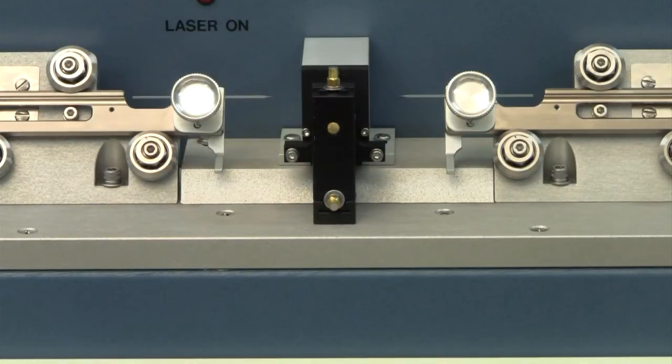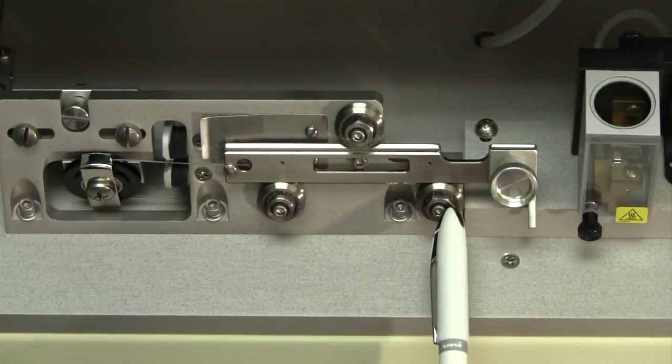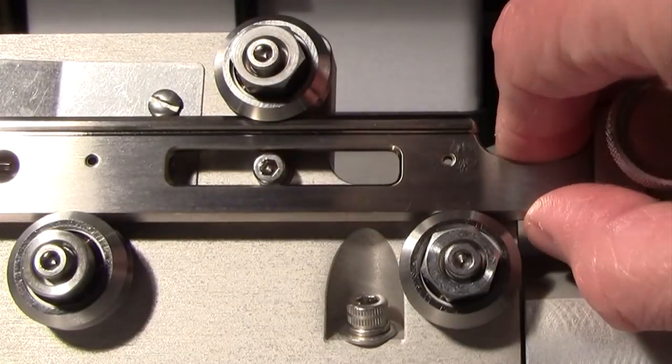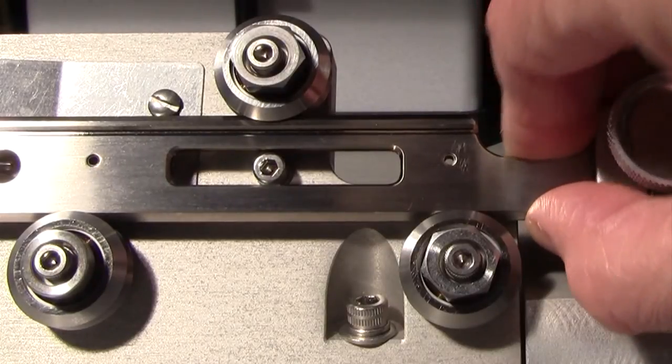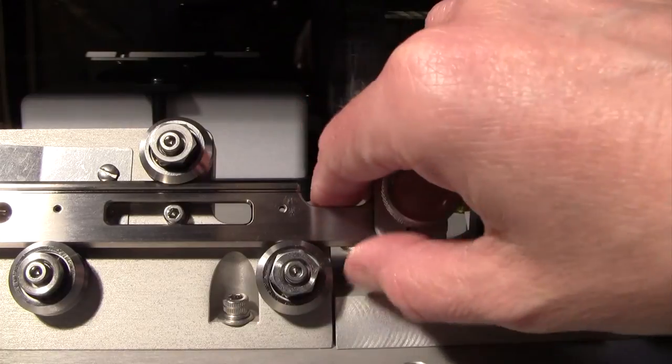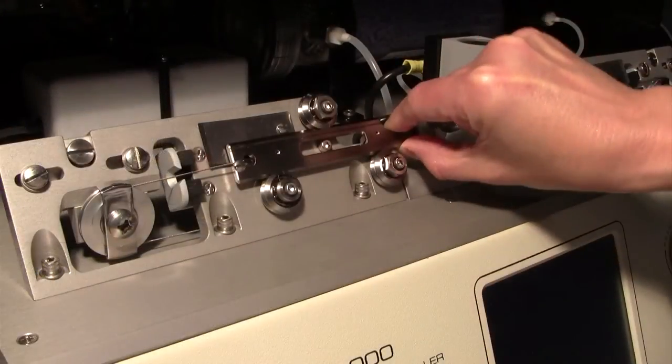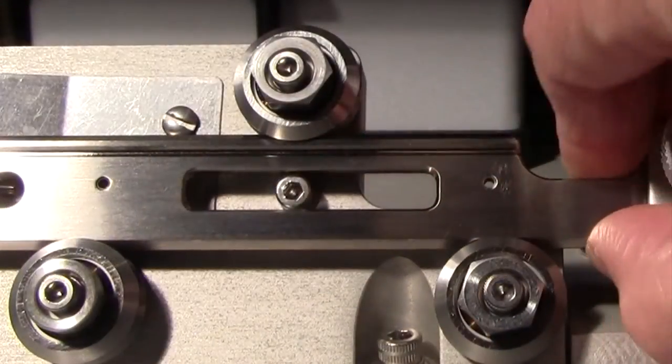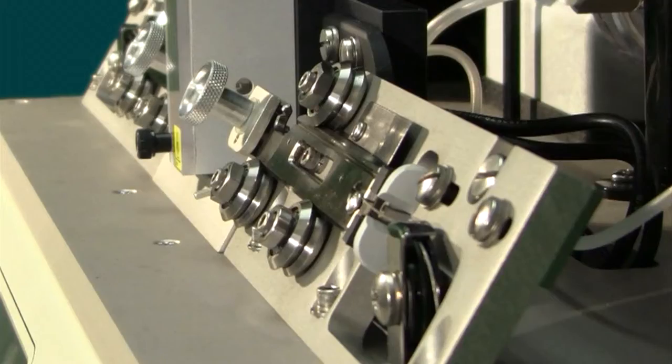To achieve this, each puller bar is carried by three V-groove bearings. The puller bars must have some vertical play in the V-groove bearings. To test this, unlock the left and right puller bars from their spring stops. Now grab one of them at the narrow section and move it rapidly up and down. You should hear a clicking sound and clearly feel some play in the bearings.